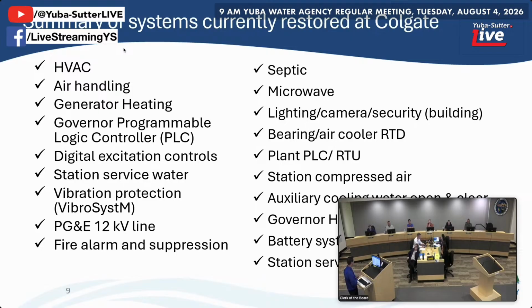Vibration protection systems are all back online. On our PG&E alternate feed, we're on normal power feed through our third means of powering our station. With both units down, we have utility power feed. Fire alarms and fire suppression systems are on. Septics and restrooms, a huge win, are fully operational. Microwave, that is our microwave communication system, is all operational, and Colgate is back online on its communication network. Cameras, lighting, and security: the elements that were not damaged are online. A number of lighting systems on the top deck no longer exist, and those circuits are still being worked through.